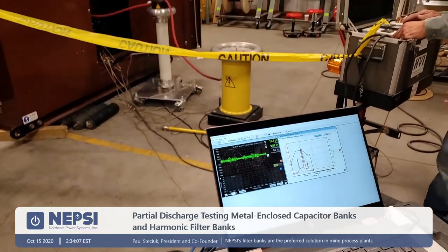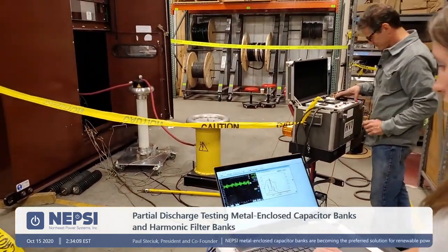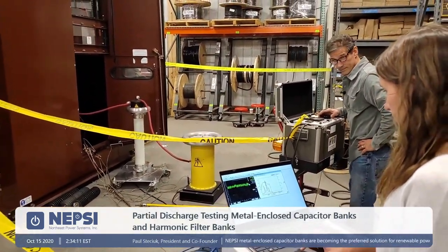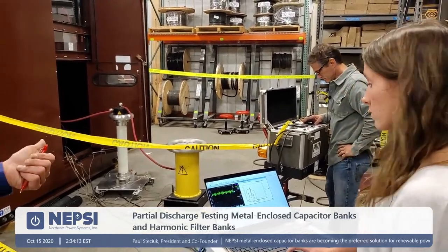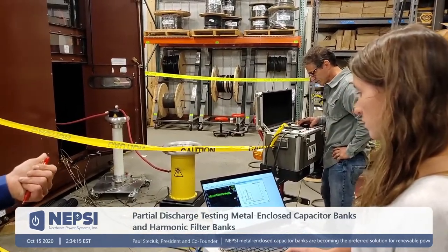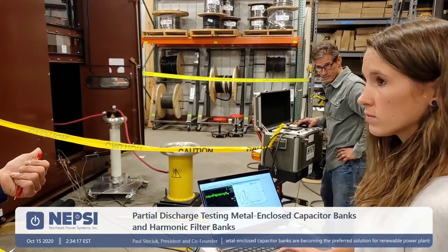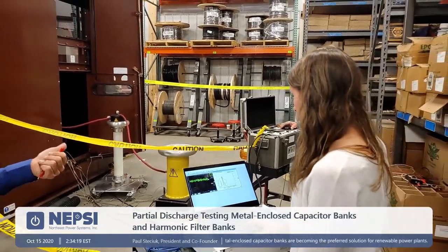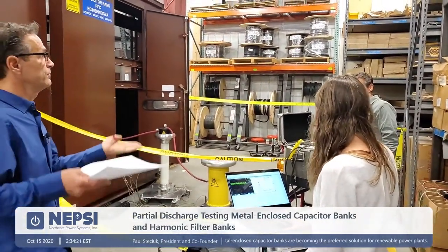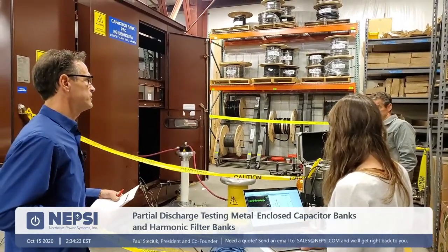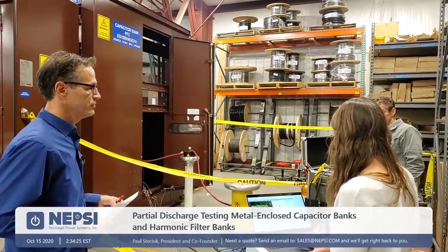All right, you ready? Yep. All right. So the objective here is you're going to bring it to 40 kV, which is 50% of the test value, 50% of the withstand rating of the equipment. At that point, there is an assumption that we're going to go into a partial discharge. Yes. And it's going to be a significant partial discharge.